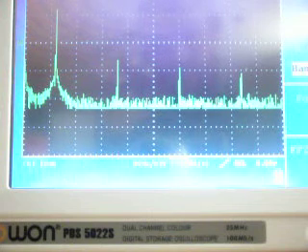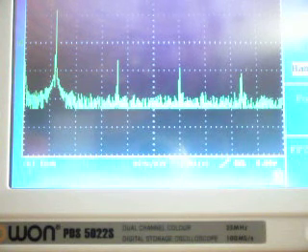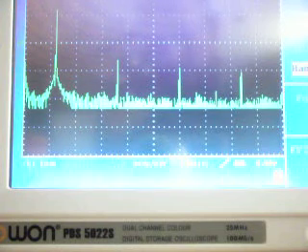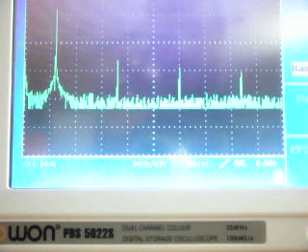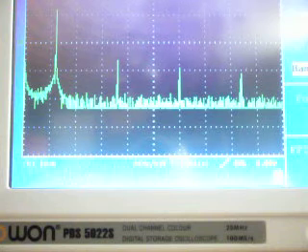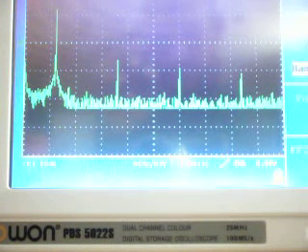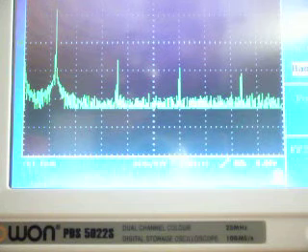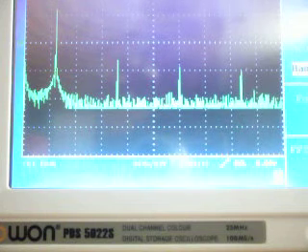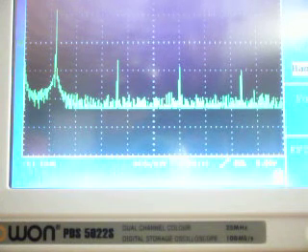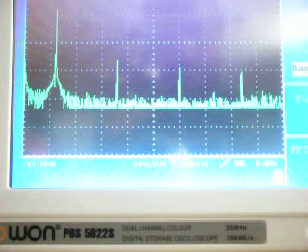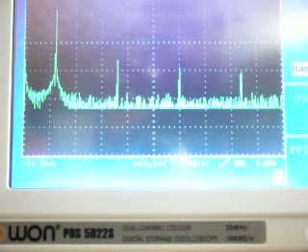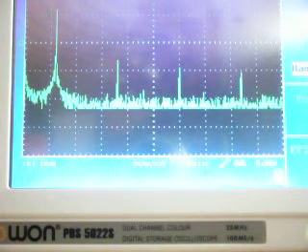As you can see, there is some dirty electricity feeding into my home right now, which is very characteristic of inverter systems. If you connect an oscilloscope onto an inverter system, you'll generally see these harmonic effects. It may be a sign that there are a lot of inverter systems connected to the power distribution system in the area.